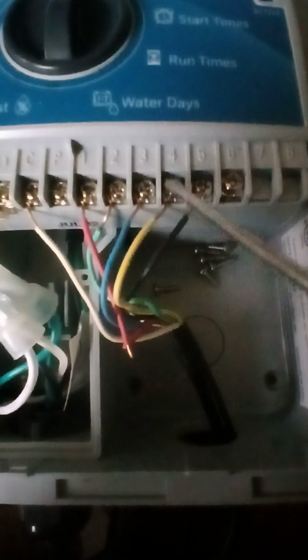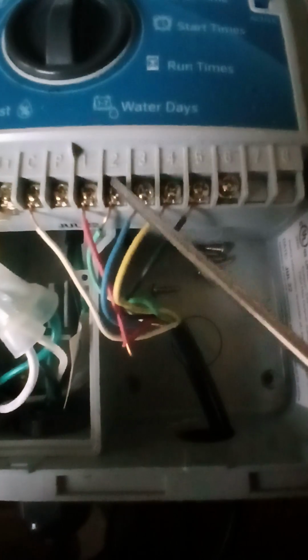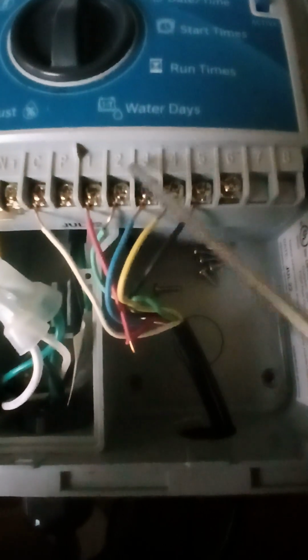Now, if you don't have a P, you can forget it, and then zone 1 would come on. In this one we have 5 zones wired up, but say if we only had 2, one would come on, then 2 would come on. But if we had a master valve, it would be connected to the P here, and I'm wondering if P comes on and takes precedence over 1, 2, 3, 4, however many zones you've got. If any HVAC guys can add that to the comments, that would be wonderful.